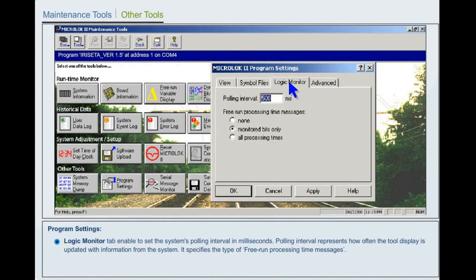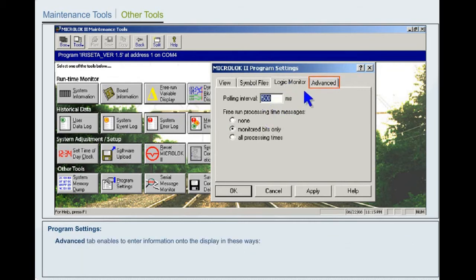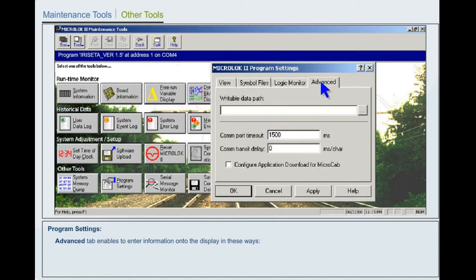Logic Monitor tab enables setting the system's polling interval in milliseconds. Polling interval represents how often the tool display is updated with information from the system. It specifies the type of free run processing time messages. Advanced tab enables entering information onto the display in these ways.